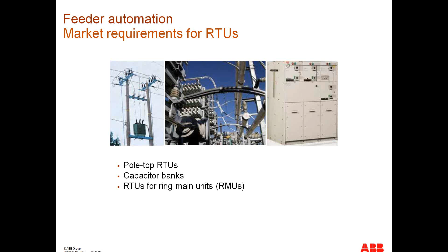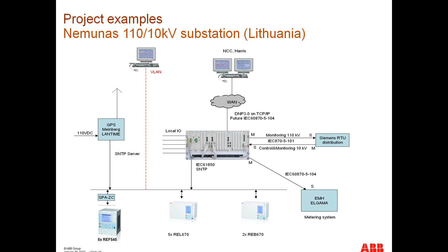Here I want to show some real projects. This is one project from Lithuania. We have the RTU as the central point in this system, and as you can see, the RTU here, from ABB, is also connected to an RTU from Siemens, another vendor, and speaks with different devices at the bay level, as well as over a WAN to the network control center, which comes from GE Harris. This picture shows how different vendors work together in one substation automation system.